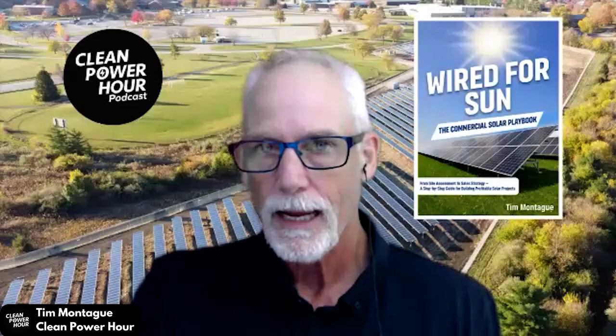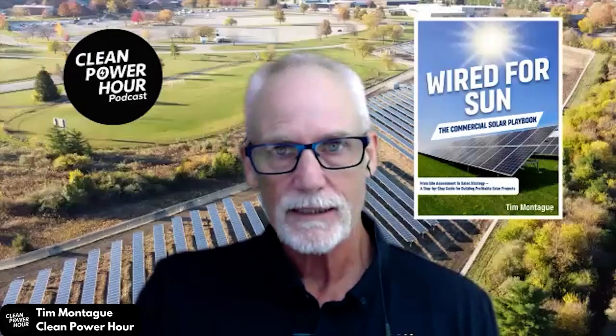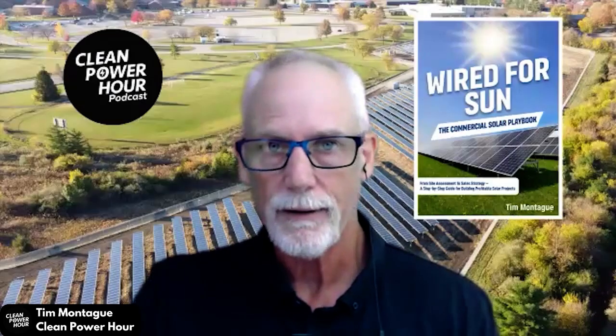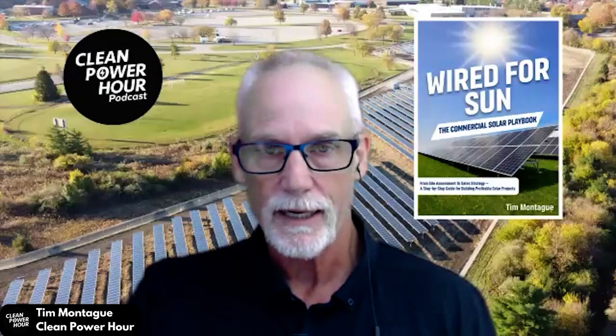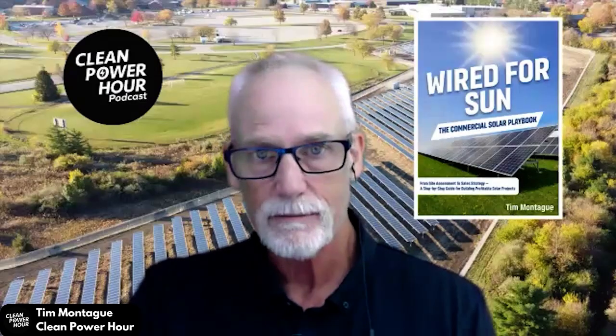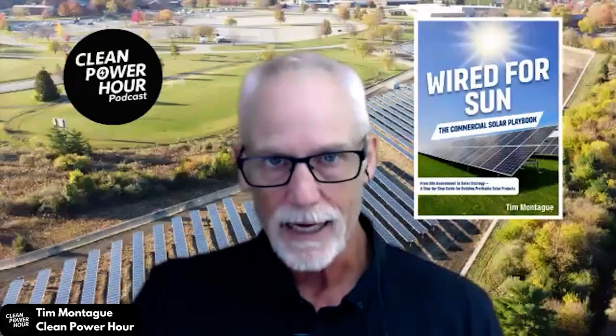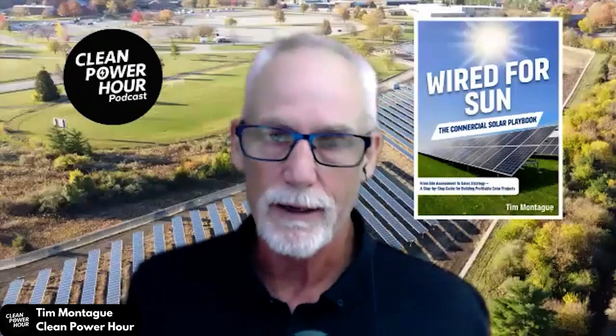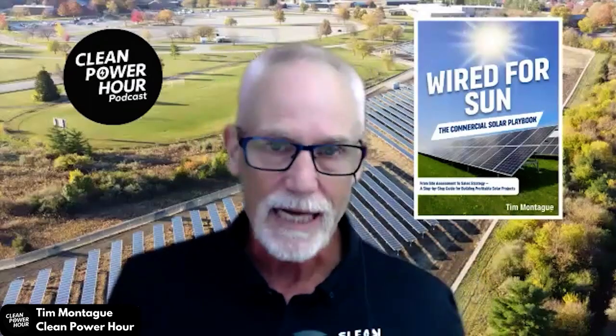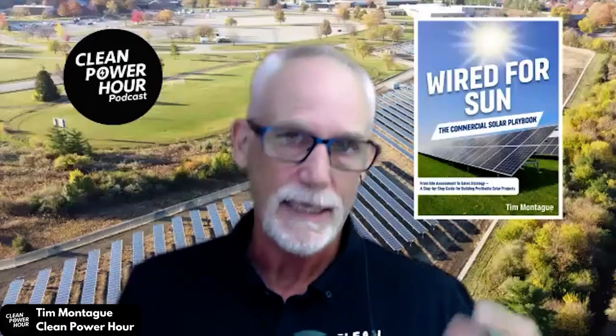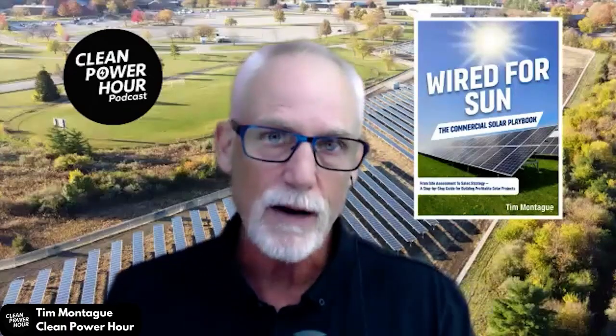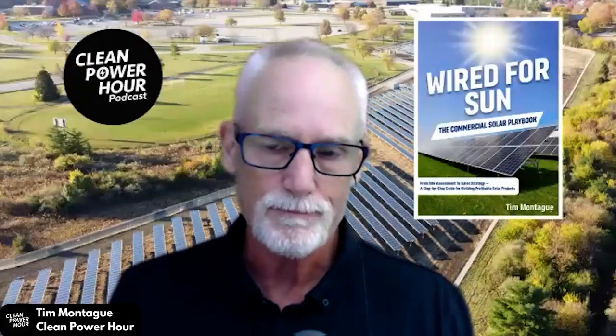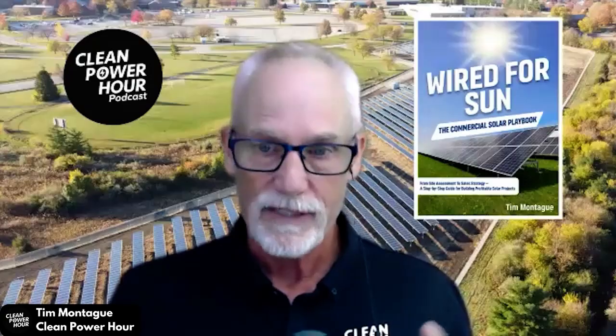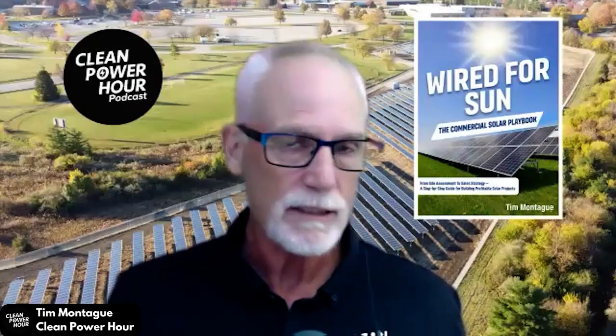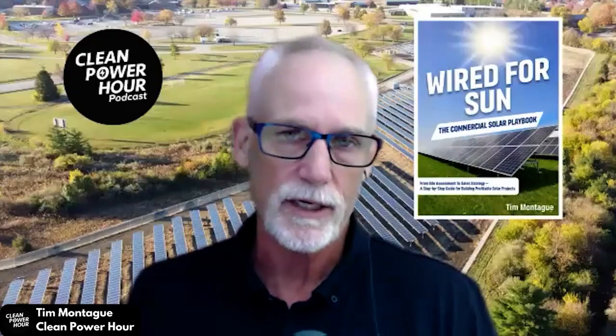Another thing we haven't talked about: when you're designing a solar system from the ground up for, say, an industrial facility that's closed on Sunday with no big load that day, that solar array is going to backfeed onto the grid. The grid infrastructure may not like that - there may not be capacity. You can use the battery as a buffer to prevent or reduce the amount of electricity injecting onto the grid, which can facilitate permitting and reduce the upfront cost of your solar interconnection.